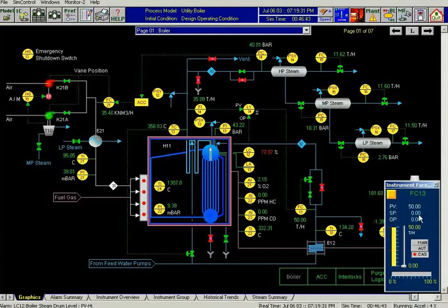The flow controller has the right set point. The flow controller asks the control valve to close fully, since the output of the controller is also 0. So the control valve should be fully closed. But this is obviously not the case, because we have a huge flow of 50 tons. Hence, there must be some problem with the valve, which seems to be completely open instead of fully closed. What should we do now?